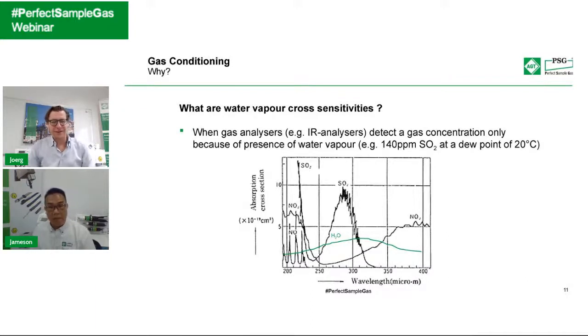I'm a practical person, as you know from the background. There are a couple of reasons - especially for those measuring SO2 when the plant shuts down after 24, 48, or 72 hours. You can see on the analyzer side, many times, that SO2 is still reading a certain milligram or ppm. So apart from that, there's a memory or carry-over effect.